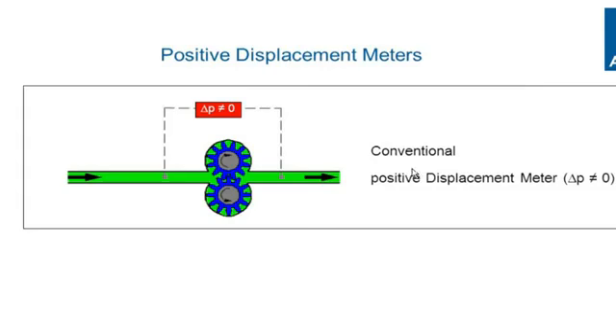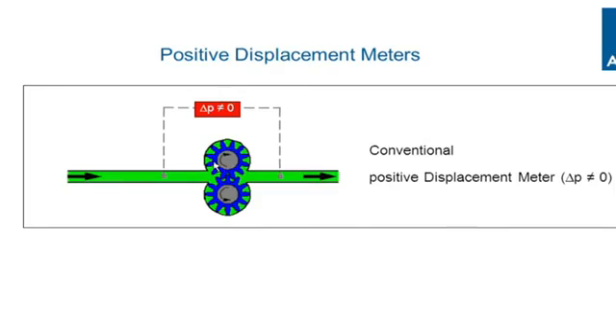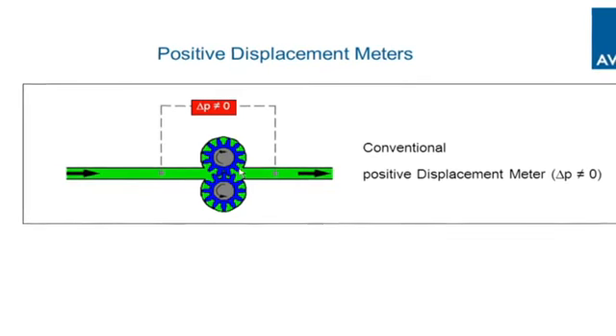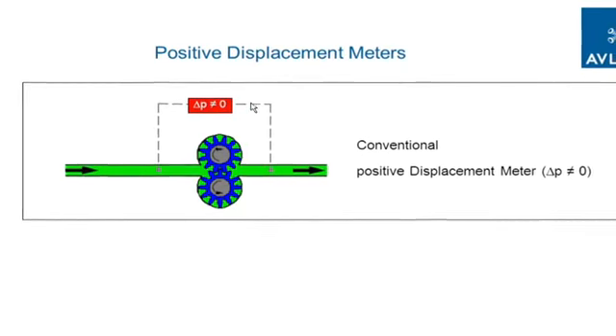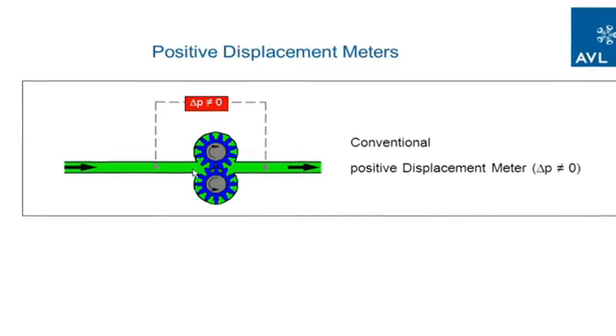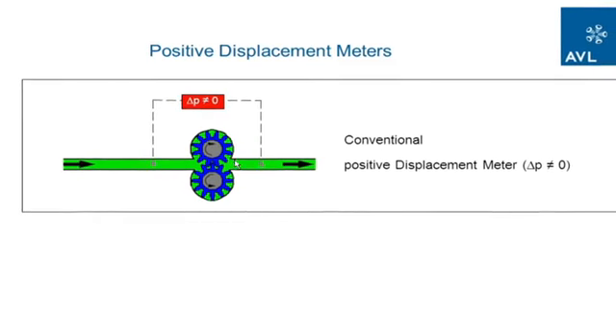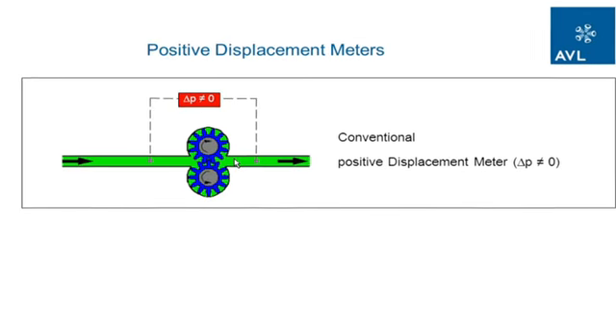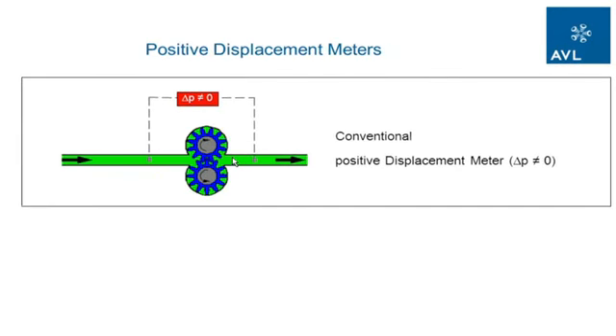The conventional positive displacement meter takes the energy from the fuel flow. That means it's driven on by the fuel flow, and the result is you will have a pressure drop above this meter. And if you have a pressure drop here, then a part of the fuel passes this gear without any counting, and this is a leakage, and this leakage is directly a measuring fault. And this measuring fault is not always the same. It changes if the density, the viscosity or the temperature change.